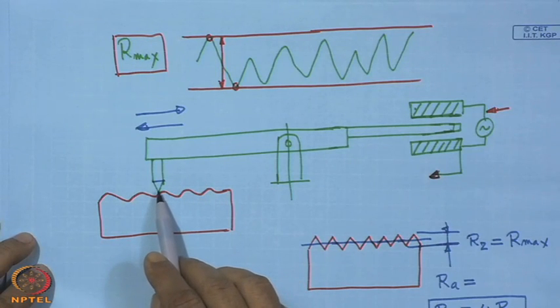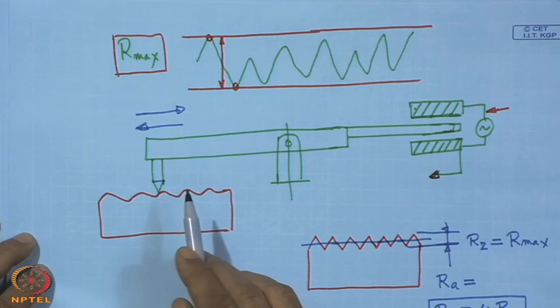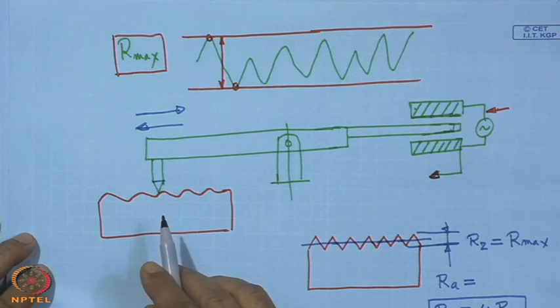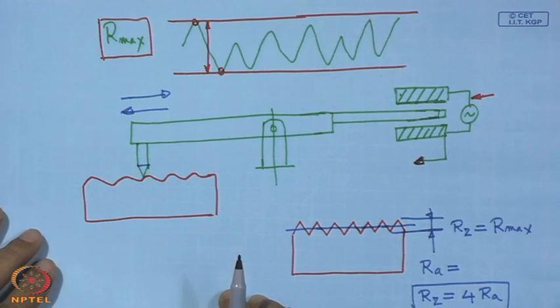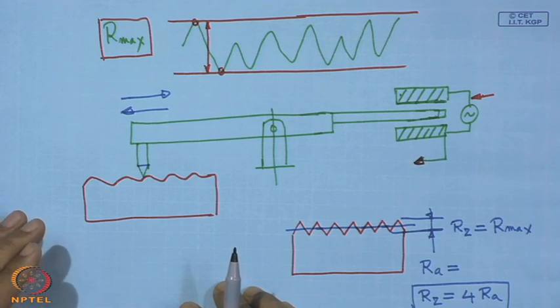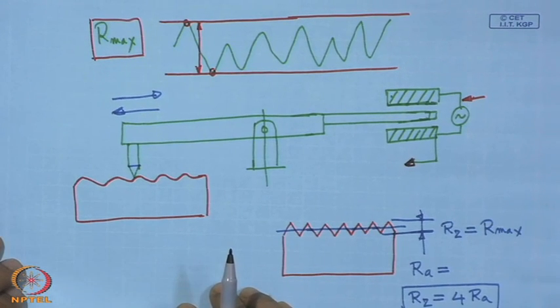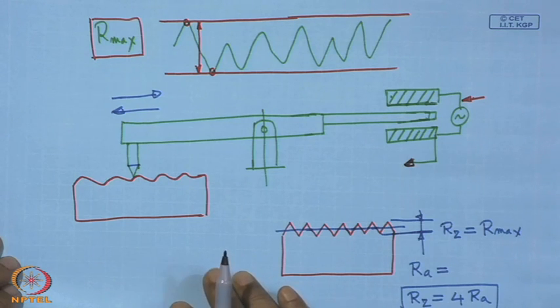Number three is the limitation of the tip radius of the stylus. For micro detailing at the micrometer or nanometer level, if the surface has many sharp corners and micro details, the stylus may be limited in recording all those micro details, and those will be rounded off. However, for comparison of two surfaces, just for assessing whether it is rough or smooth with reasonable accuracy and quantification, these machines are quite convenient and reliable for all sorts of engineering applications.